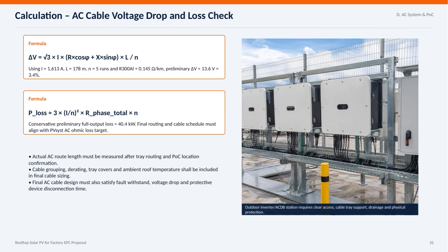It's important to note that the final routing and cable schedule must align with the PVsyst AC ohmic loss target to ensure efficiency. Additional considerations include measuring the actual AC route length after tray routing and point of connection location confirmation. The final cable sizing must account for cable grouping, derating factors, tray covers, and the ambient roof temperature. Also, the final design of the AC cable must meet fault withstand requirements, voltage drop limits, and protective device disconnection times to ensure safety and reliability. Finally, outdoor inverter and AC distribution box stations need clear access, cable tray support, proper drainage, and physical protection to maintain system integrity and ease of maintenance.